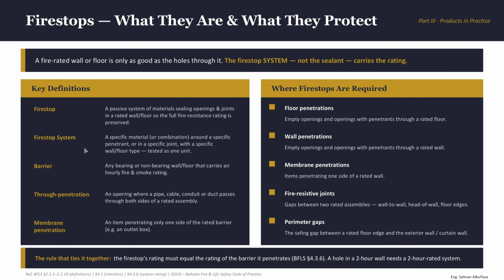But what people miss is firestop is a system. A system is a specific material or combination of materials tested together as one unit. What we mean by tested as one unit is we cannot mix products from different manufacturers. We cannot mix stuff that is not tested together as one assembly. And a barrier is simply any wall, any floor that carries an hourly fire and smoke rating. Basically, the thing we're trying to protect.